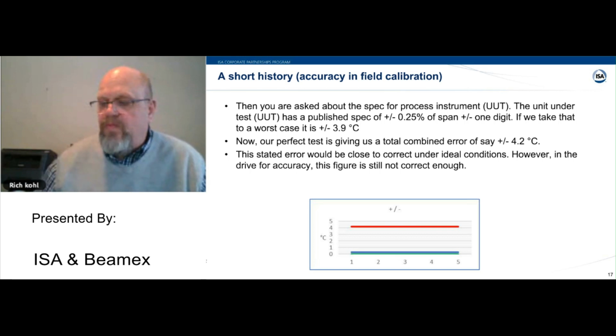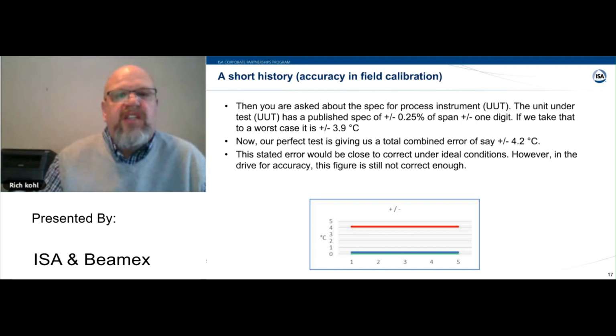Now you're asked about the process instrument, or the UUT, the unit under test. It has a published spec of 0.25% of span, plus or minus 1 digit. If we take that as a worst case scenario, we're up to 3.9 degrees C. Now your perfect test has gone up to a combined error of 4.2 degrees C. So that stated error is close under ideal conditions. However, in the drive for better accuracy, the figure is still not good enough.